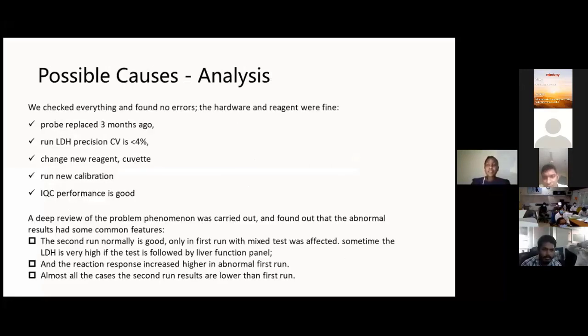So we checked everything. In our system, the planned preventive maintenance was done, and the probe had just been replaced some 3 months ago. Our precision studies for an analyte like LDH were okay. LDH had given a CV of less than 4%, which is an acceptable run as per the CLSI guidelines. The reagents were new, not stale. The cuvettes were new, not reused. Our calibration was okay. Even when we recalibrated, it was still okay. IQC performance and trends were okay. Our LJ charts were doing well as per Westgard rules.